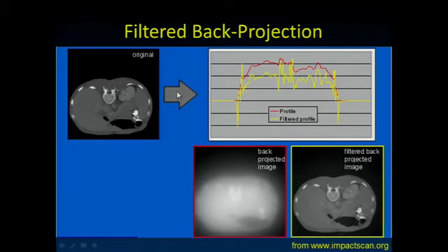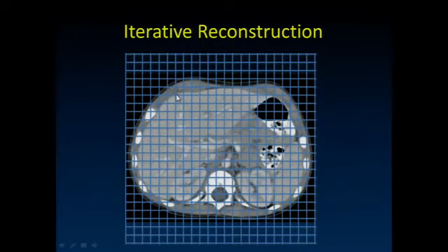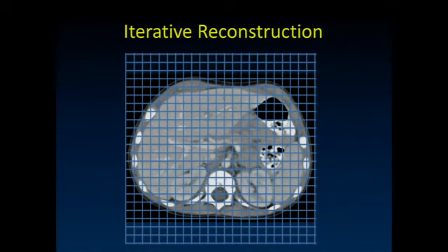We're moving more and more to iterative reconstruction techniques away from filtered back projection. The main reason is we can model the image formation process better and handle noise better. Why didn't we do this before? Because it's computationally an extremely complex problem—it takes a tremendous amount of computing power. The theoretical mathematics behind it aren't as complex as for filtered back projection, but the computational power required is much greater.